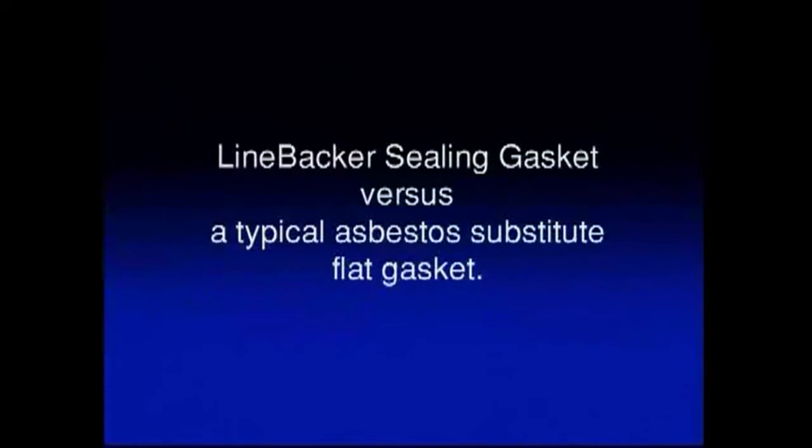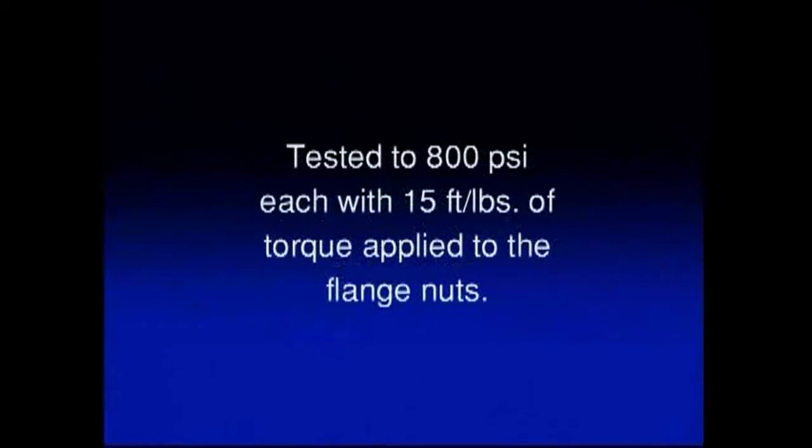We'll use a gasket tester to demonstrate the effectiveness of the linebacker gasket versus a flat gasket, each with 15 foot-pounds of torque applied to the flange nuts.